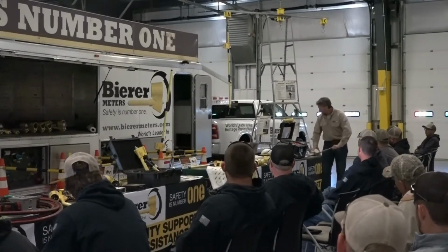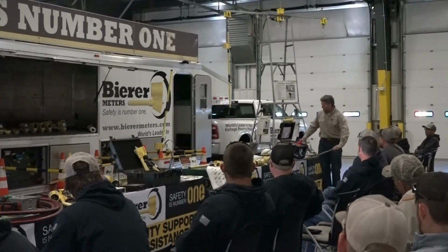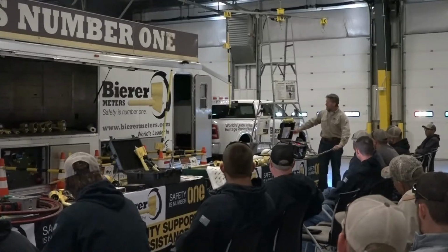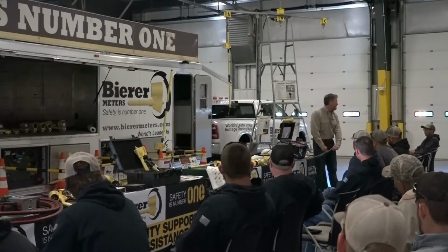We'll go a little higher, 168 amps give or take. We have a 0.21 voltage drop. This cable requires a 0.24 voltage drop or less to pass, so as you can see, it passes.